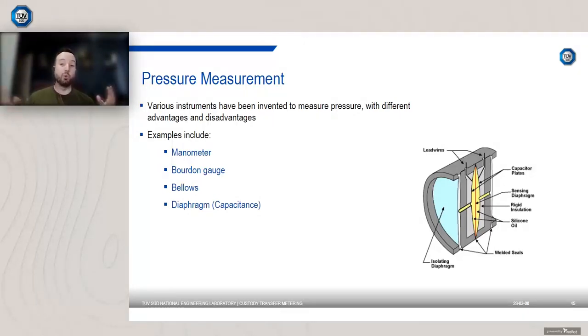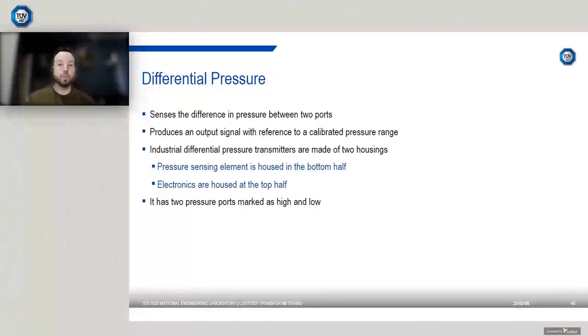Differential pressure, you've got two ports. Differential pressure, like I mentioned previously, senses the difference in pressure between two ports. When it comes to differential pressure transmitters, which are typically used in custody transfer systems, if it's an orifice package, for example, you've got your pressure sensing element in the bottom half. That might be your capacitance diaphragm sensor. And you've got your electronics in the top half, and two pressure ports marked high and low.